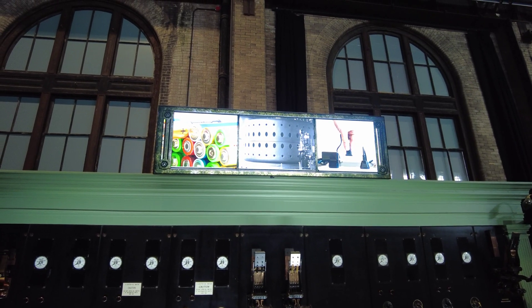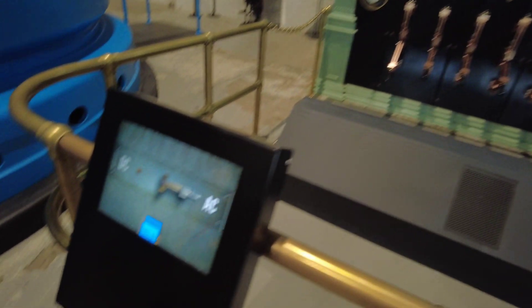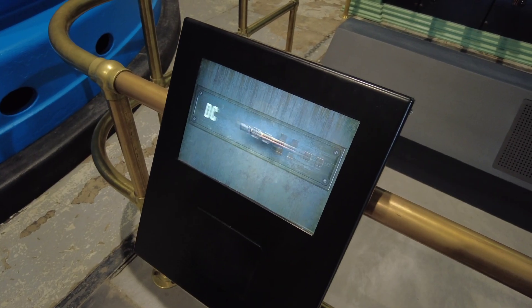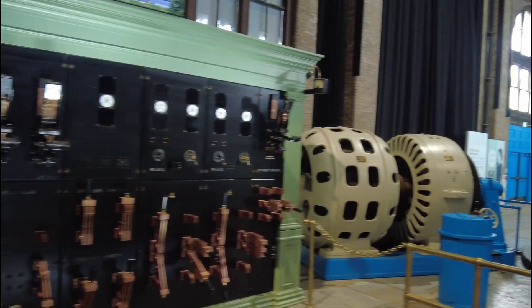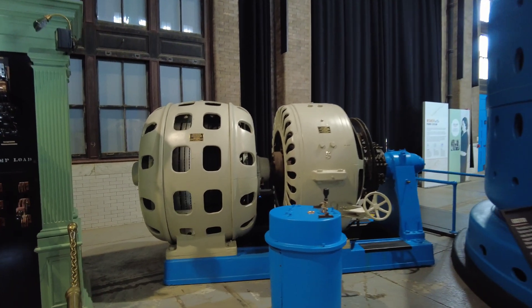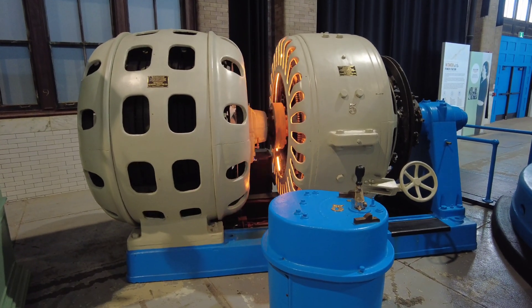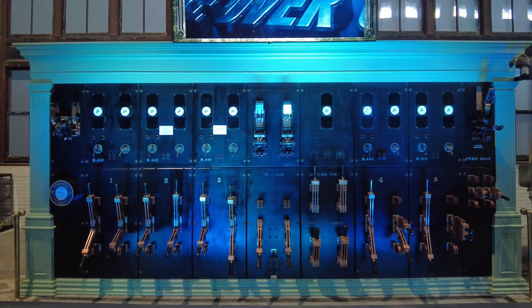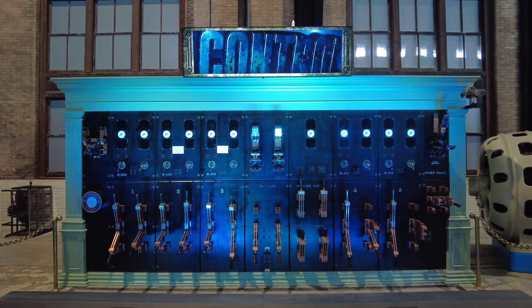Do you think we use AC or DC current to create our magnetic field? If you think it's AC, move the switch to the right; if DC, move it to the left. The answer is DC current. In this station, we make all our direct current with an exciter unit. An exciter unit has two parts: a motor on the front end that rotates a DC generator on the back end. As soon as that motor is turning, the DC generator starts spinning and producing DC power.